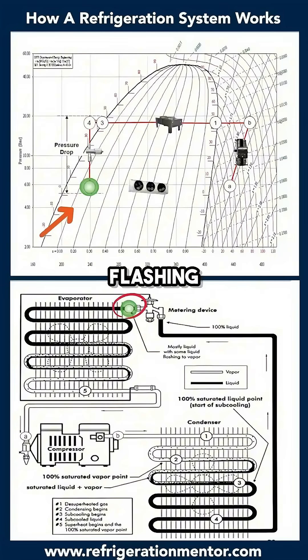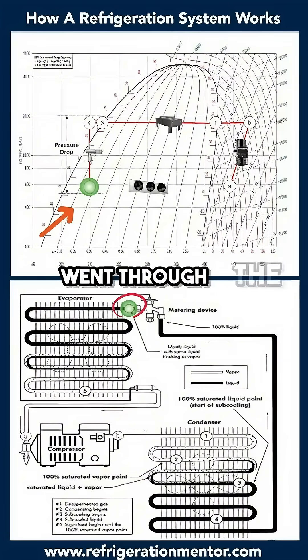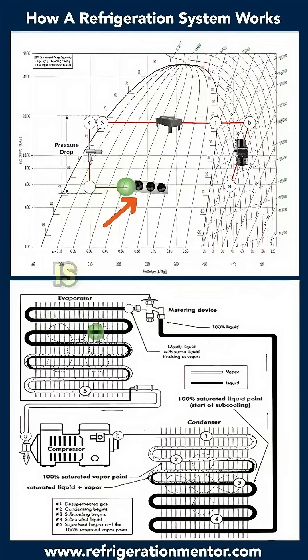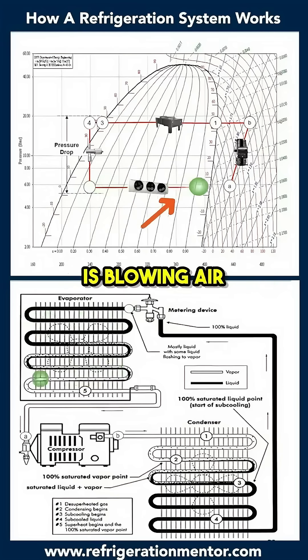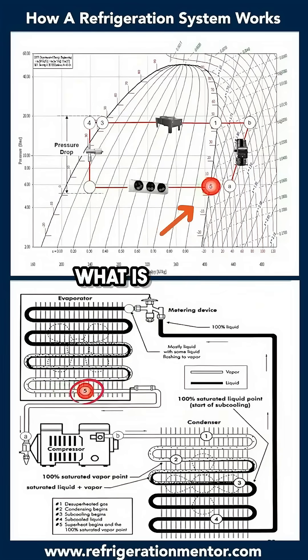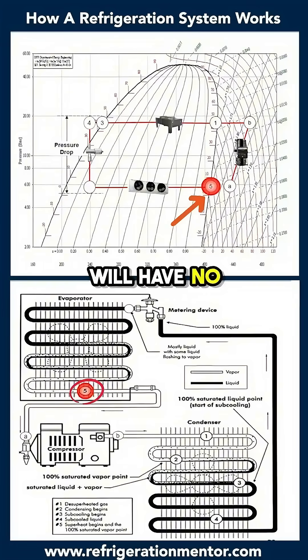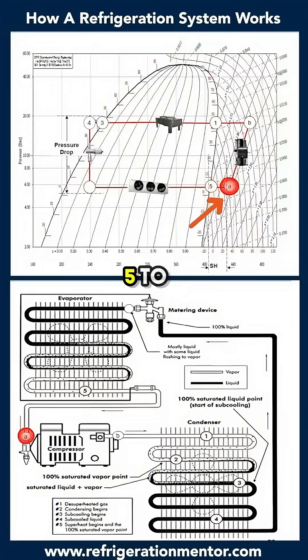It's flashing out of that TXV. As you can see, it just went through the metering device and now we're back into the two-phase region inside that thumbprint. The evaporator is blowing air over the coil, causing the refrigerant to boil, so by the time it hits that dew point again you'll hopefully have no liquid left — and now here's your superheat from 5 to A.